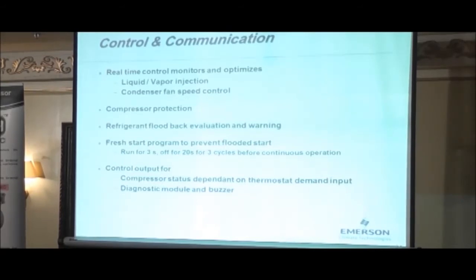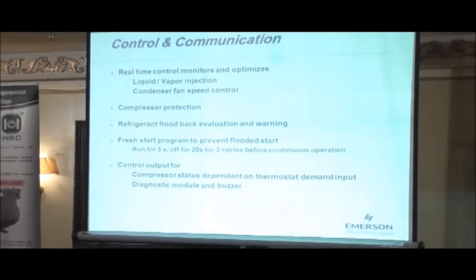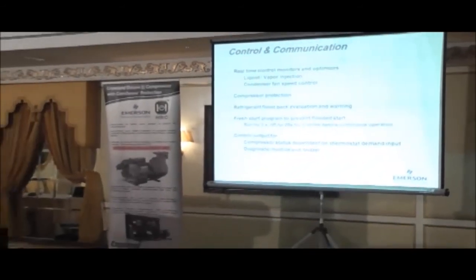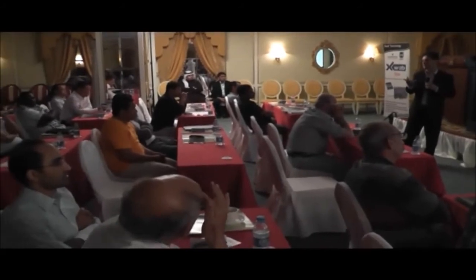One important point you've got to remember is it's got a fresh start program. Right? Every time the compressor starts up, it's going to run for 3 seconds, switch off for 20. It's going to repeat that cycle 3 times. And the reason why we do that, that if you do have a lot of refrigerant in the compressor, this is what we call bump starting. You try and get rid of the liquid before the compressor runs. So this is one safety feature where we bump start the compressor. We try and boil off the liquid in the refrigerant, and then only on the 4th time will it run, because by that time all of the liquid refrigerant will have boiled off and the oil.